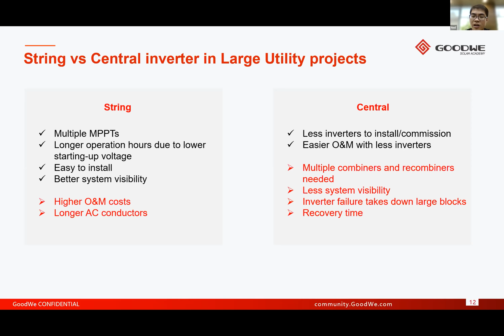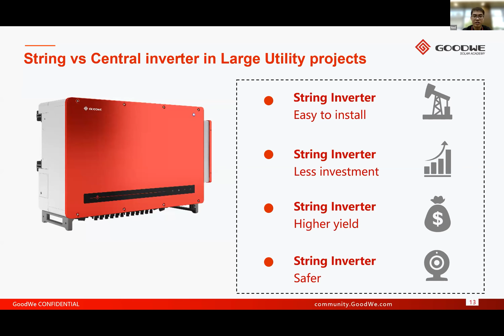Other advantages are longer operation hours due to the lower starting-up voltage, easy installation, and better system visibility. But the disadvantages are high O&M for distributed locations of inverters and longer AC conductors. But with string inverters' flexible design in large projects, we have solutions to make up for the disadvantages. Now we can see string inverters are easy to install, less investment, higher yield, and safer. But also with the emergence of new tracker technologies and bifacial panels used in the power plant, the string inverter will have added advantages. Keep in mind that the string inverter costs are also coming down. We believe the trend in the inverter market will be more string inverters being used, and the shift is happening.